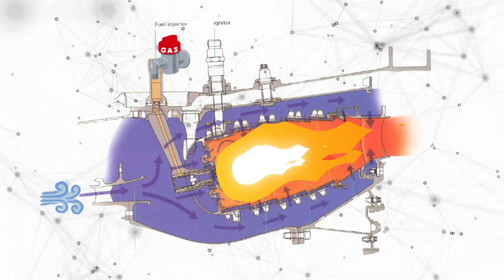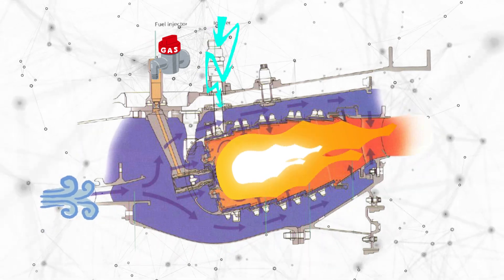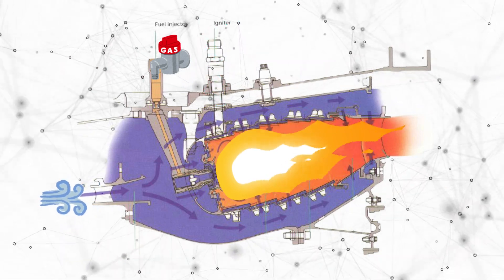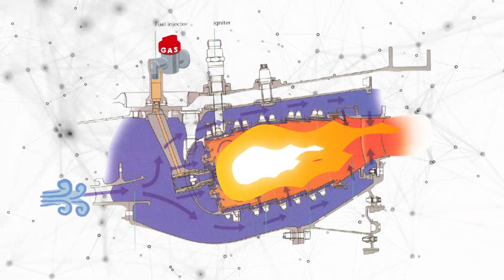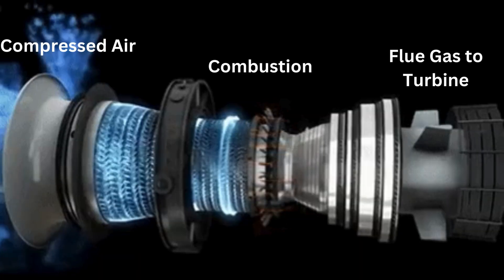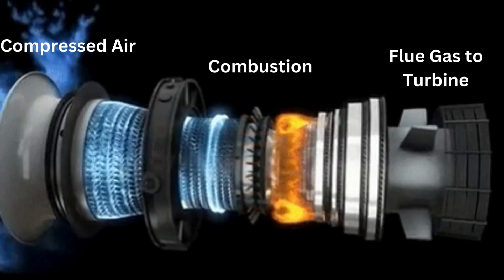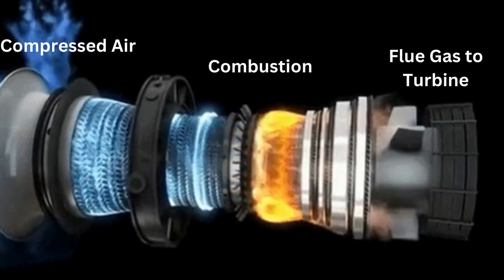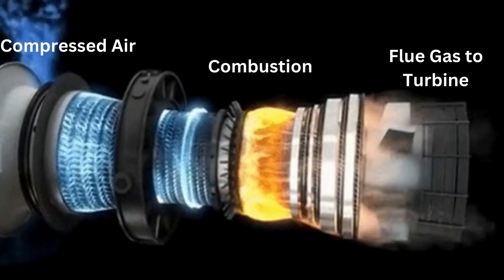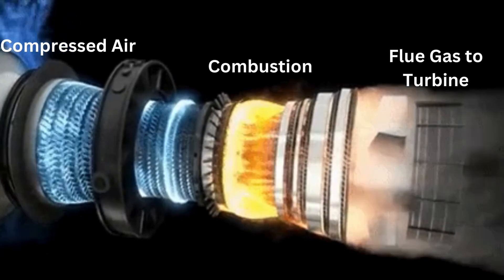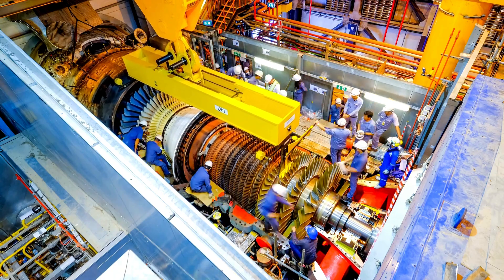The combustor facilitates combustion in primary, secondary and dilution zones. Designs include annular, can-annular and silo types. Turbine Inlet Temperatures (TITs) can reach up to 1,700 degrees Celsius, managed by superalloy blades and advanced cooling technologies. Real combustors also experience pressure and temperature losses, impacting overall efficiency.